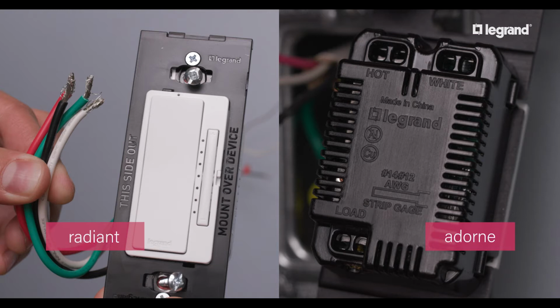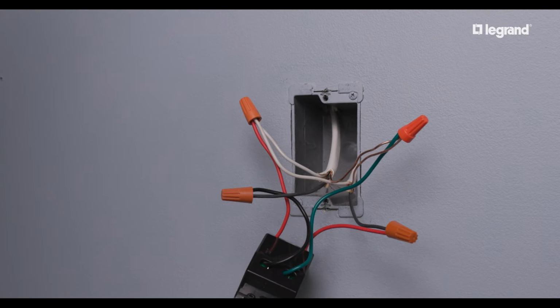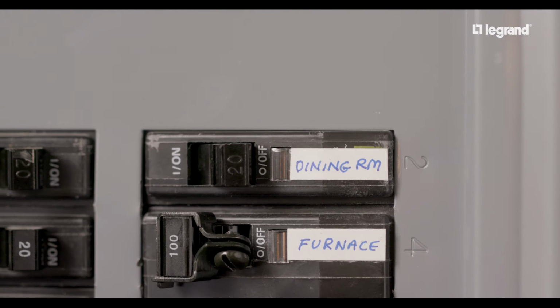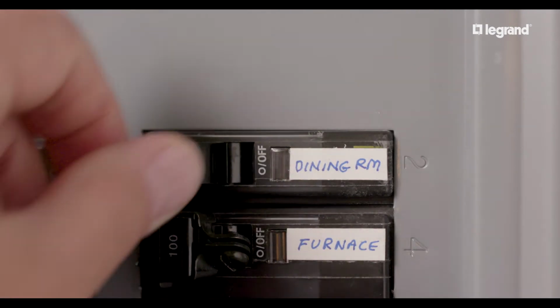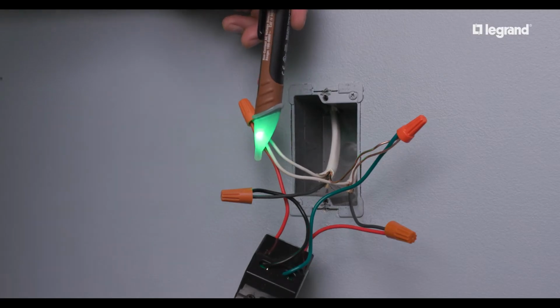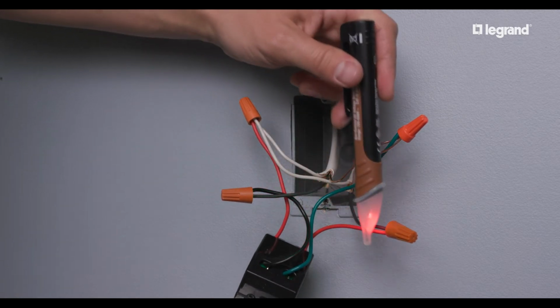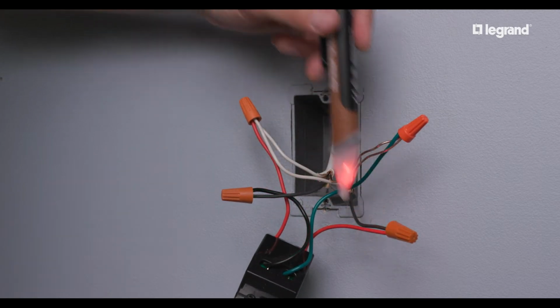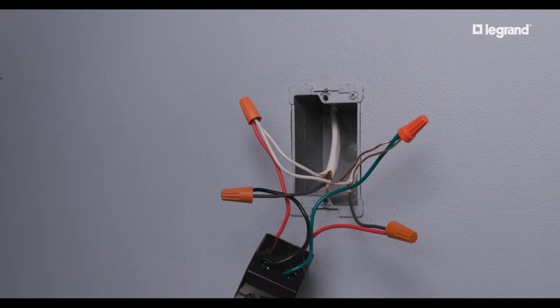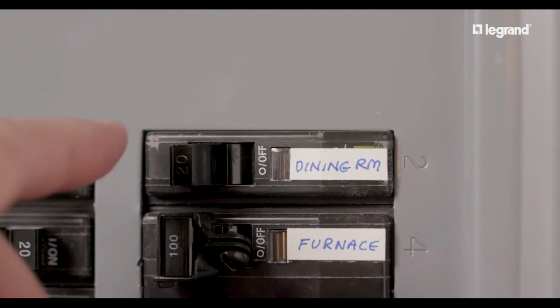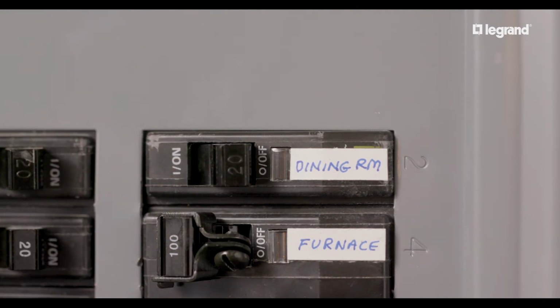In both cases, you'll be connecting the neutral wire, the load wire, the hot wire, and the ground wire to your device. In your wall, it's important to note which wire is the hot wire and which is the load wire. To do so, turn the circuit breaker back on. With the light switch off, test each wire with the voltage tester. The wire with no power is the load wire, and the wire with power is your hot. Now that you've determined which is which, go back and turn off your circuit breaker.